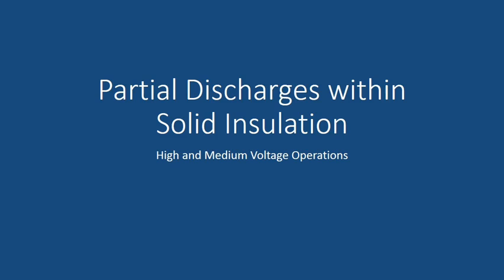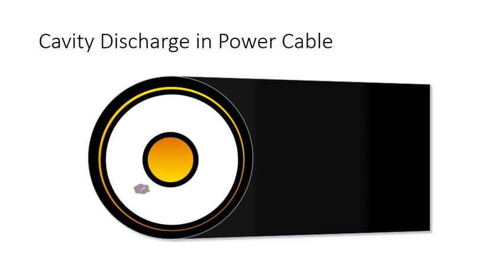Solid insulation with impurities and air-filled gap cavities can be found in solid insulation of medium and high voltage generators, motors, and power cables. Insulation defects are a result of manufacturing, handling, and other faulty processes. Under power cable operations, cavities experience localized electrical stress — partial discharges.